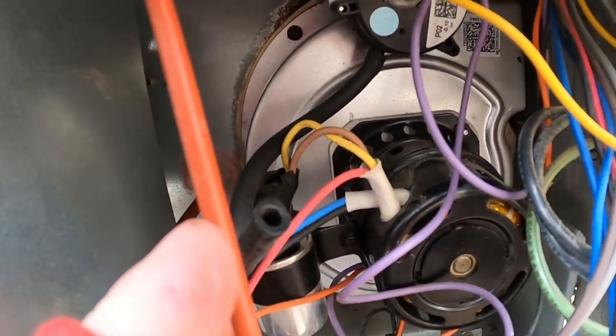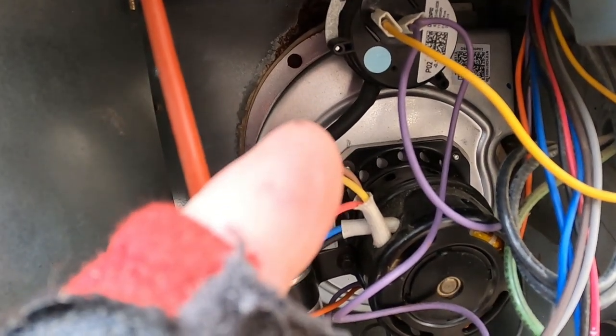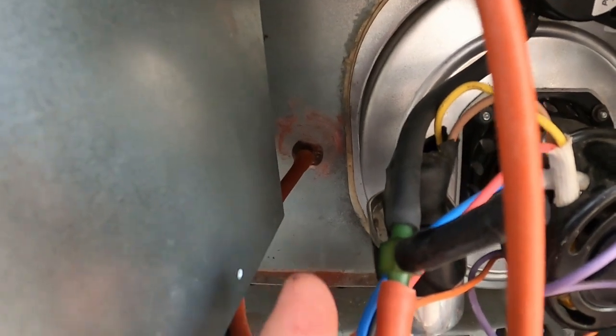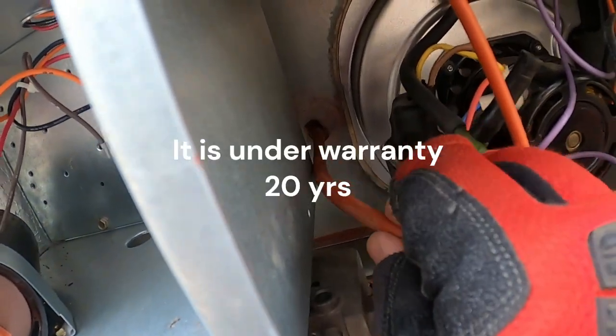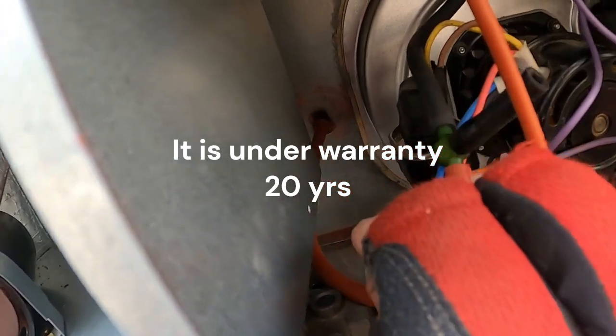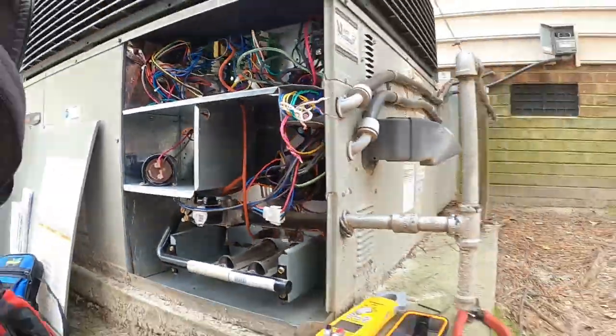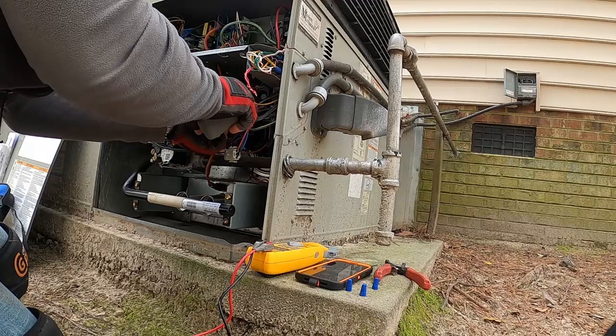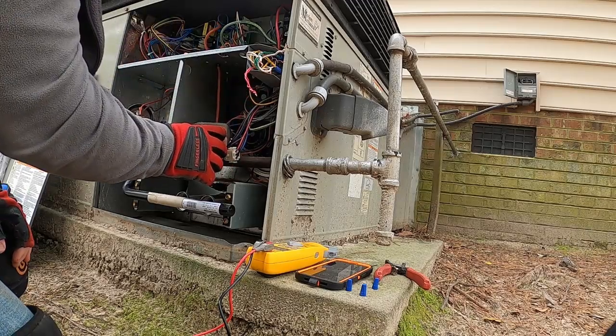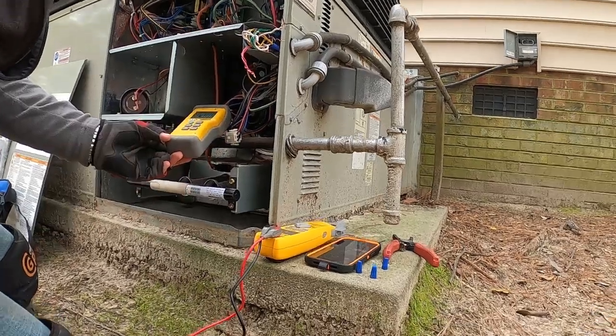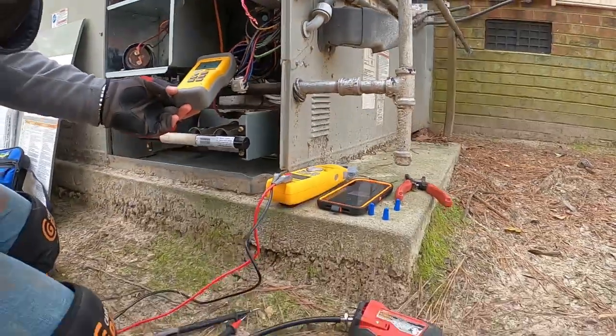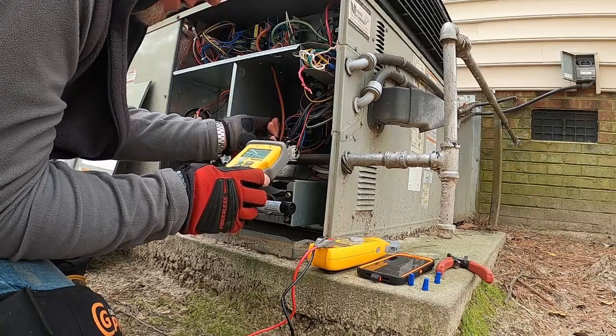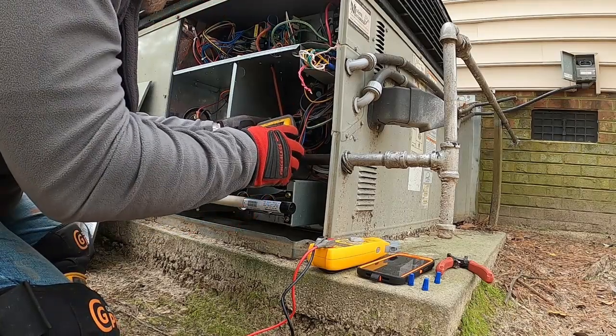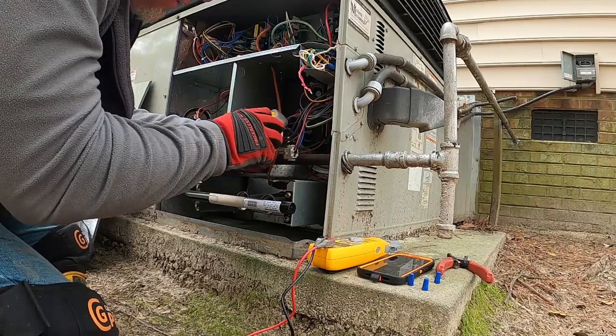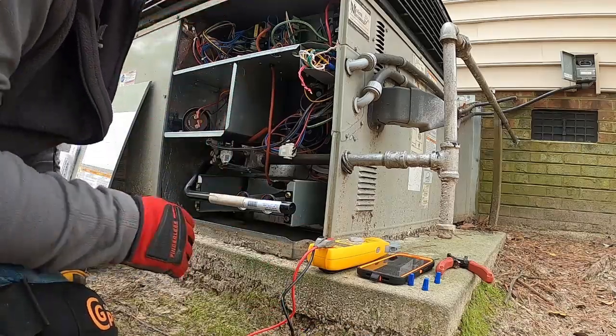And they changed and put the inducer motor where your hose port goes on the inducer housing to the pressure switch instead of the front of the face panel, because those things were rusting out. The only way to fix that is to replace the heat exchanger faceplate. So it was just a bad design on Trane, and that's why they changed it. But anyway, I'm checking in line between there and the pressure switch. I'm getting a 0.25, 0.26. Should be a lot stronger than that, I would think. 0.27. So that thing being loose probably has something to do with it.